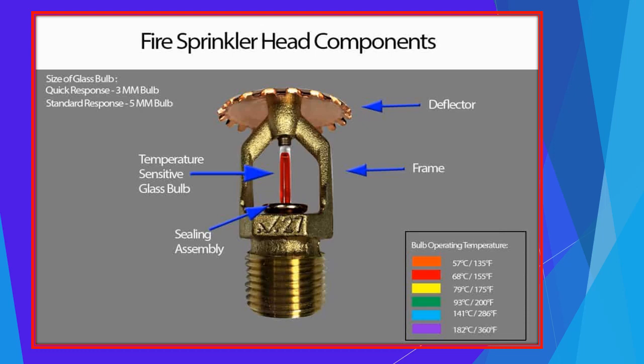In this slide, we are going to have the explanation of your sprinkler head itself, how it actually looks and what is happening. You can see over there, this is the deflector plate, and this is your complete frame. This is your temperature sensitive glass bulb which will shatter and the water will start flowing. This is your sealing assembly which holds the water. As for the size of the glass bulb, it is a quick response 3 mm bulb, or a standard response 5 mm bulb. You can see the color coding given over here. This is your orange one, 57 degree centigrade.